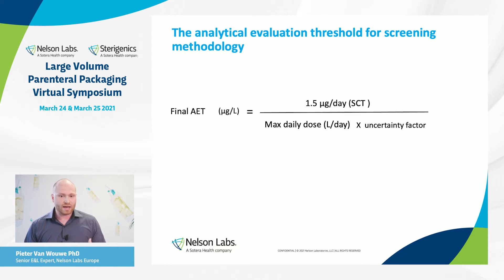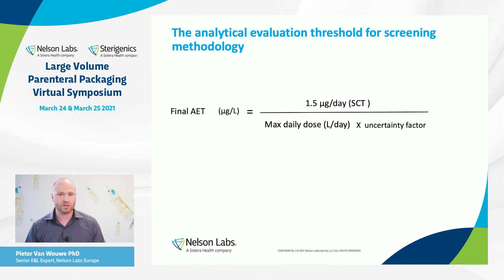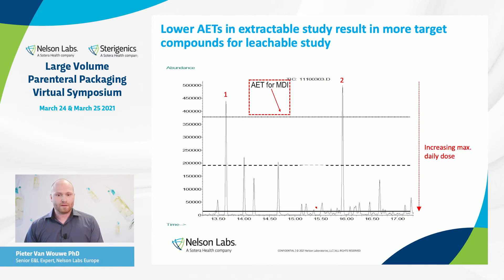All PQRI values are expressed as a daily intake. We need to translate that into an analytical value for our extractable/leachable studies — that is the AET. You can calculate it by dividing the safety concern threshold by the maximum daily dose. We typically use screening methodology for E&L studies, and therefore need to introduce an uncertainty factor to arrive at the final AET. If we go to applications with a higher daily dose, the AET will also significantly drop in a proportional way.